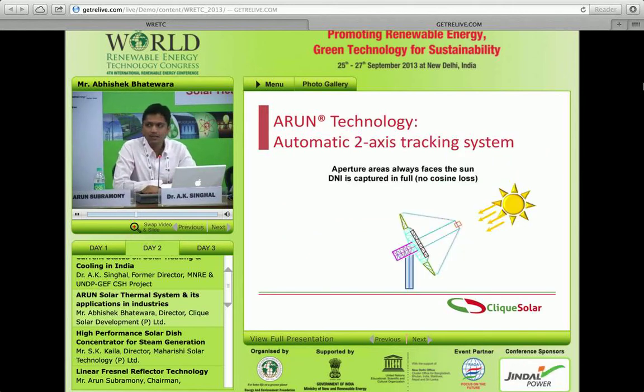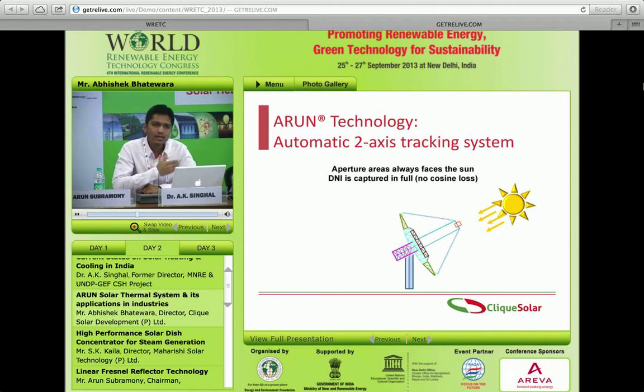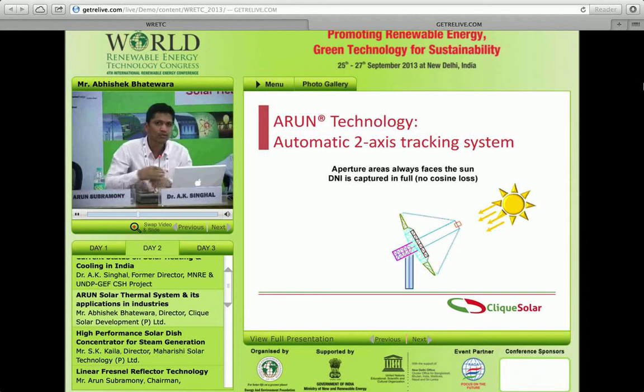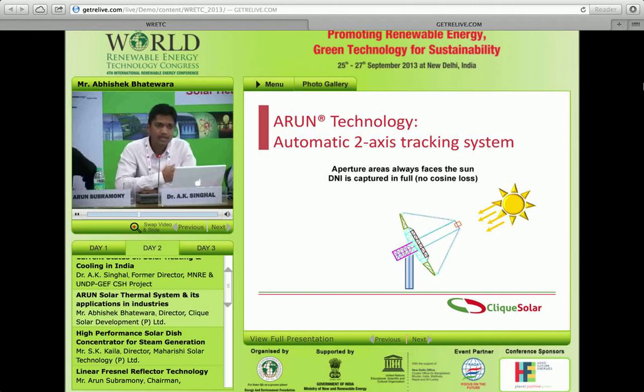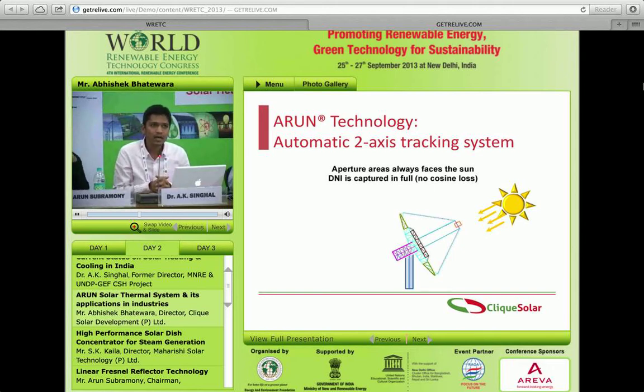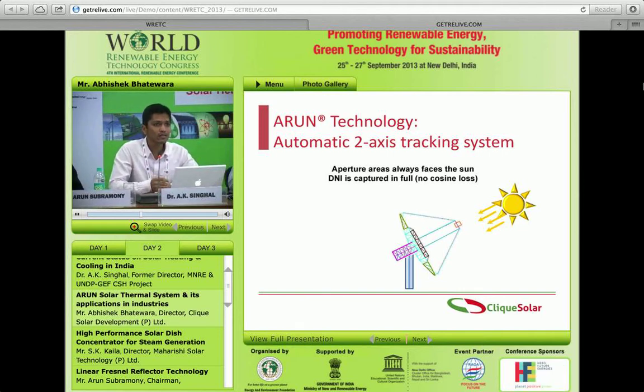The third aspect of the technology is tracking. This is a two-axis automatic tracking system. The sun doesn't move in the same plane in January as in June — the plane of the sun shifts. There is east-west tracking every day — that's the single-axis tracking — and it also moves along with the seasons, which is the second axis. As a result, the dish surface is always facing the sun at 90 degrees, capturing maximum energy at all times of the year.